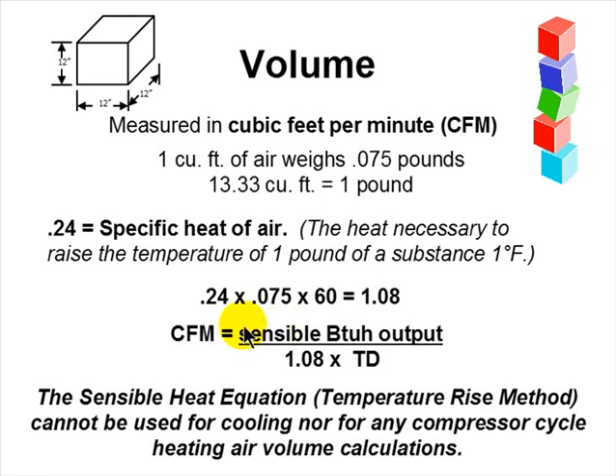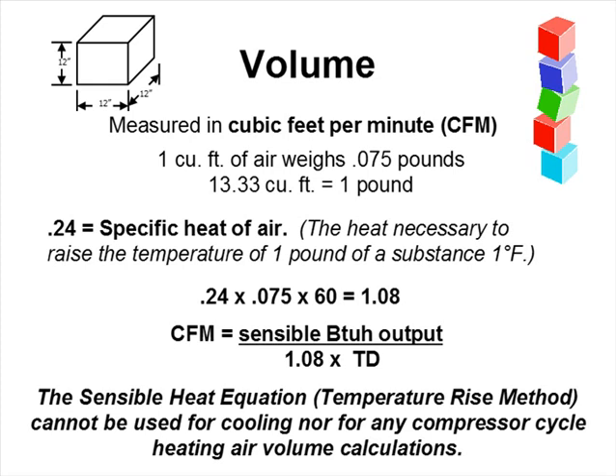When we have an air conditioning unit, it is removing both sensible and latent heat. It would be almost impossible in the field to know what portion was sensible and what portion was latent — even if you knew the sensible heat ratio, that only applies at steady state. For instance, when is a three-ton unit actually three tons? On a 95-degree day after running an hour, or on an 80-degree day after five minutes? You cannot apply this formula any time you're dealing with vapor compression — heat pumps in cooling season or straight condensing units.